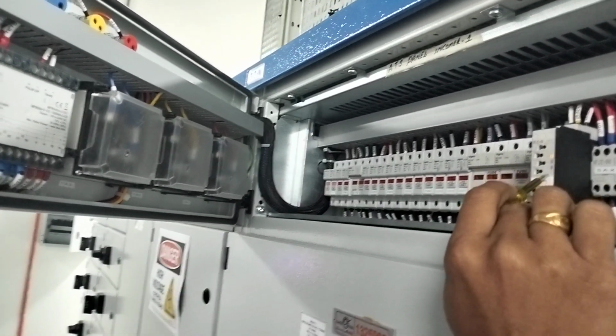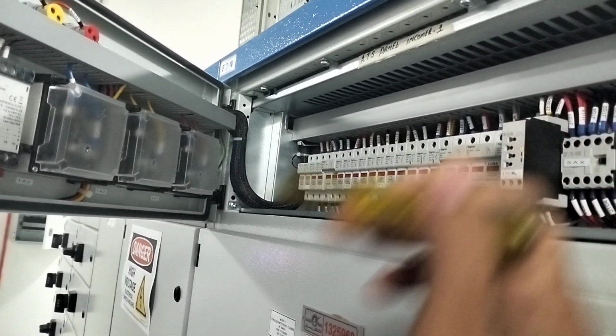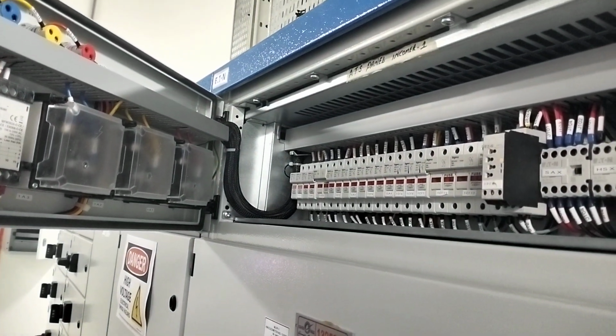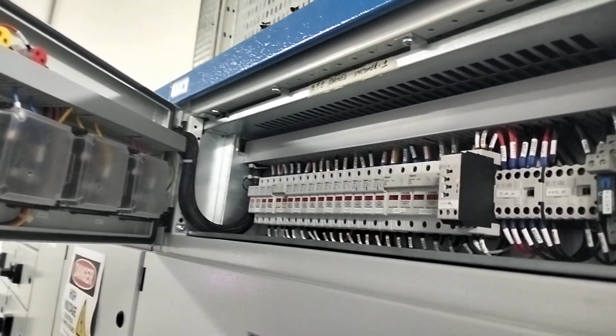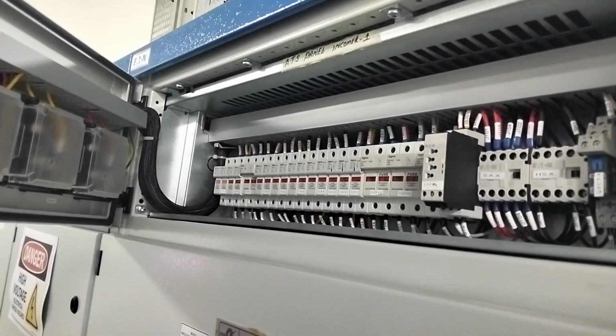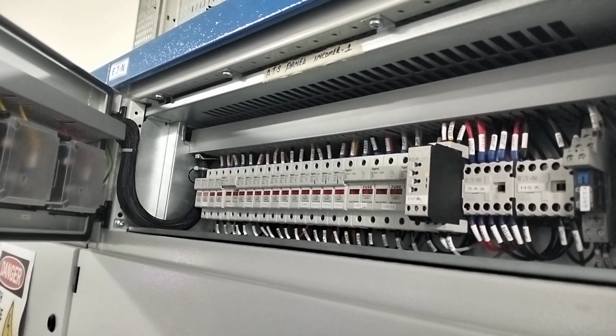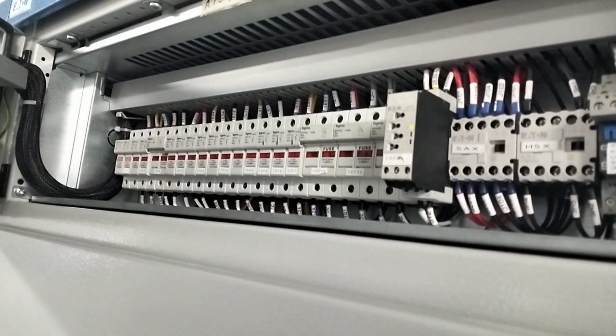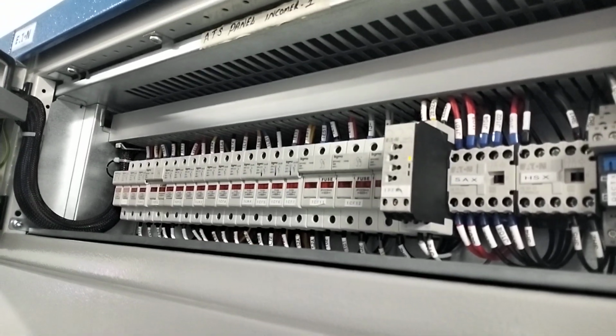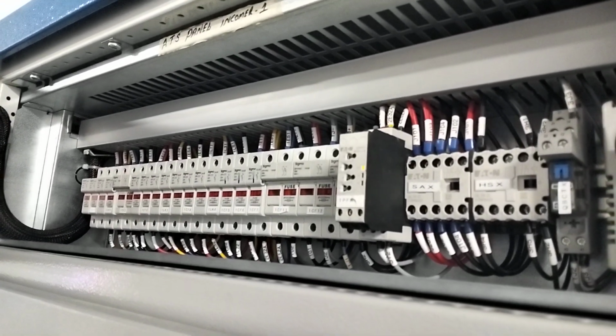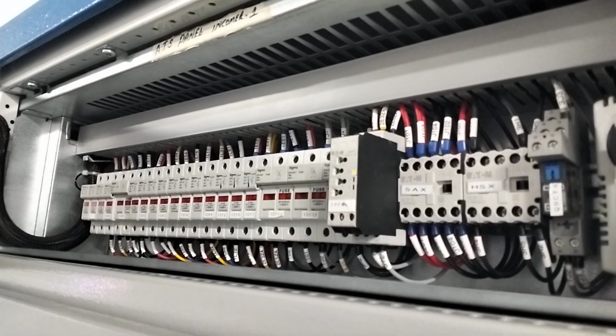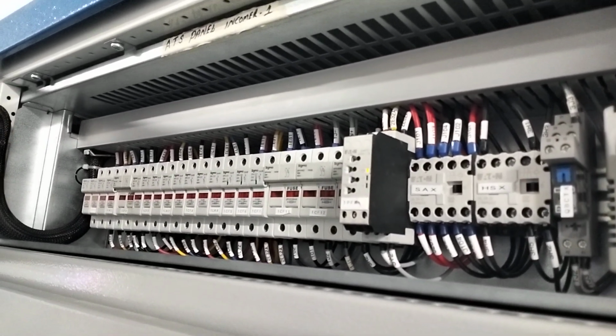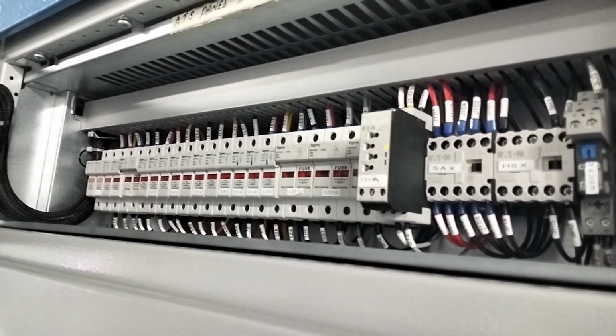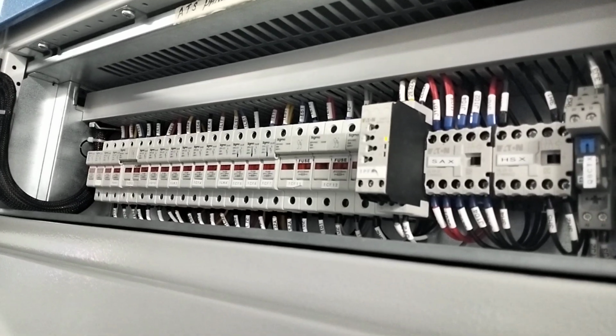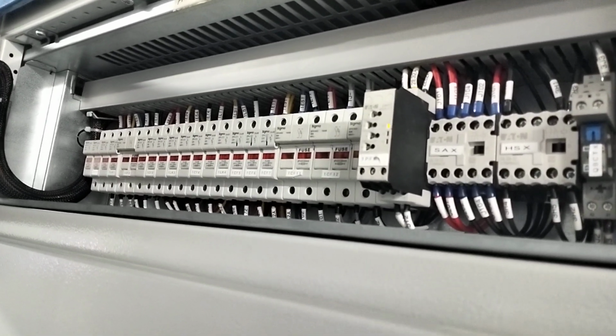When this relay is giving the under voltage signal, what will happen? If you are in automatic mode, the generator will start. Any voltage failure, voltage fluctuation or under voltage or phase failure, phase sequence problem, anything. So does this directly give a command to the generator? No, this goes only to the ATS. There are two contacts wired to the generator side. If the relay gives the contact to the generator, it will start.